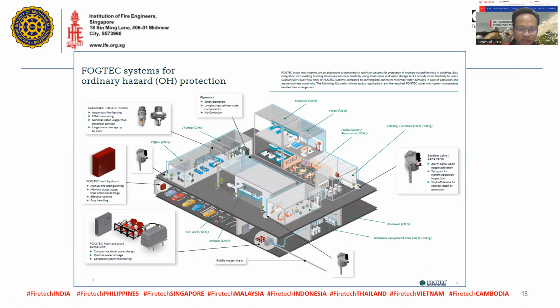For IT, maybe you put a clean gas suppression system. For a museum, you can put a clean gas suppression system. For the common area of the parking, you're going to put a sprinkler system. However, if you use a water mist system, everything is protected by a water mist system. Thereby, you will not have a multitude or variety of systems, but only one water mist system with one centralized pump. And that's it. You're not dealing with gases, but with high pressure water. Imagine the OPEX, the operational expenditure. I believe it has a lot of savings in it as you have the system for quite a while.